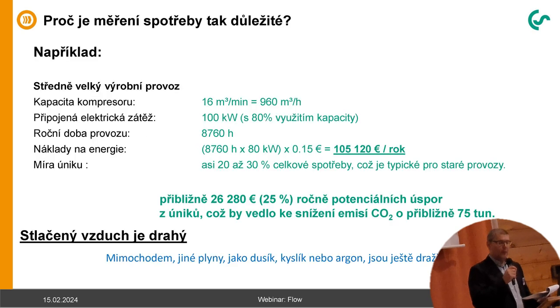So we have made a little example, or a little calculation. If you have a small company, for example, with 150 people working there, and they have a compressor capacity of 16 meters cubed per minute or 960 meters cubed per hour, this is approximately a compressor with 100 kilowatt. So in 100 kilowatt, let's say they only work with 80% capacity, we can calculate with 80 kilowatt. But if they have a 3-shift system working 24 hours a day, you will come to the conclusion that this very small company already has a compressed air cost of 105,000 euros per year.